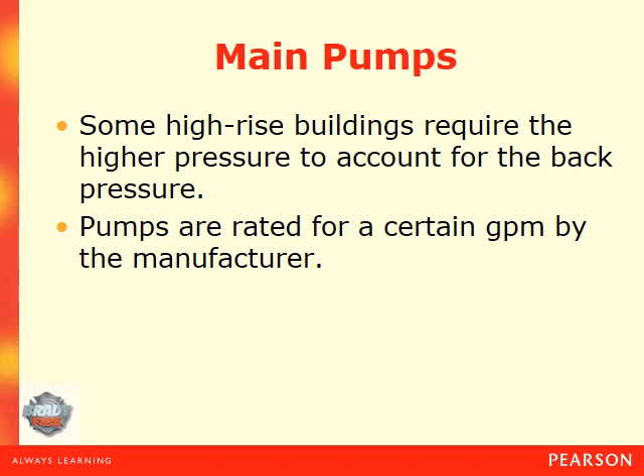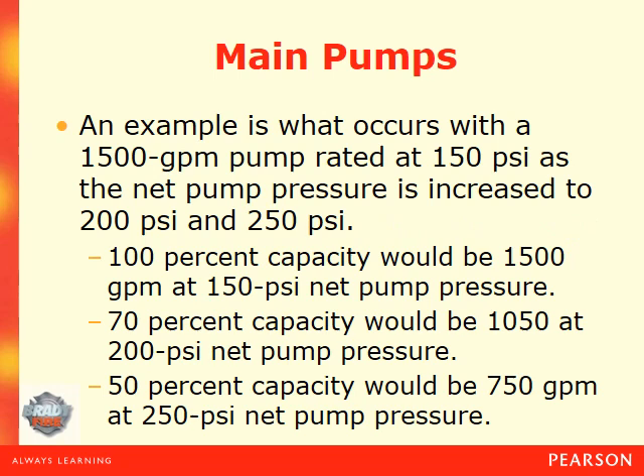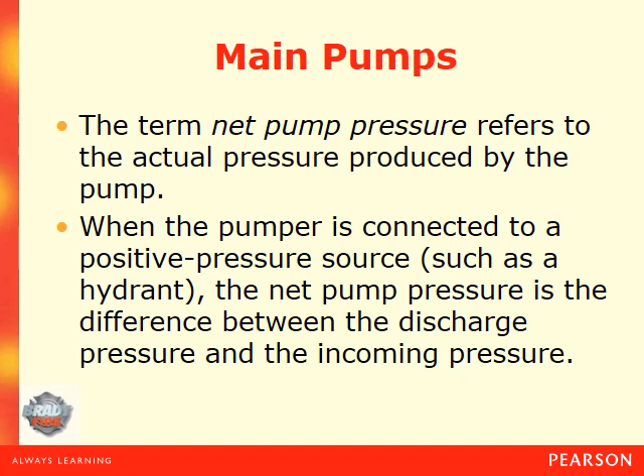Pumps are rated for a certain GPM by the manufacturer, into three different pressures. Their capacity test is at 150 psi where the pump will pump its maximum gallons per minute. Then you have 70% of capacity at 200 psi and 50% capacity at 250 psi. For example, with a 1,500 gallon per minute pump rated at 150 psi: 100% capacity would be 1,500 GPM at 150 psi net pump pressure; 70% capacity would be 1,050 GPM at 200 psi; and 50% capacity would be 750 GPM at 250 psi net pump pressure.